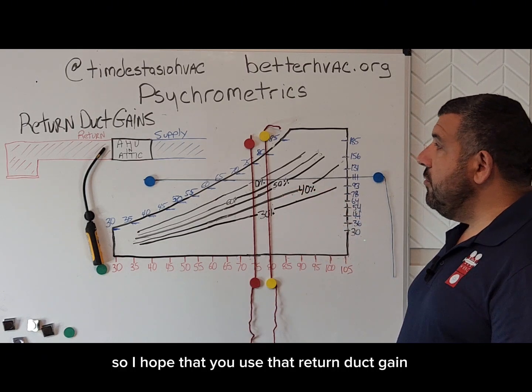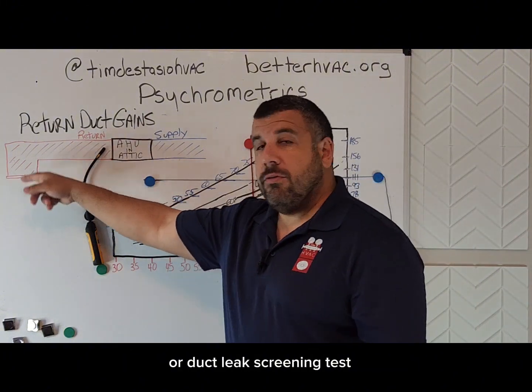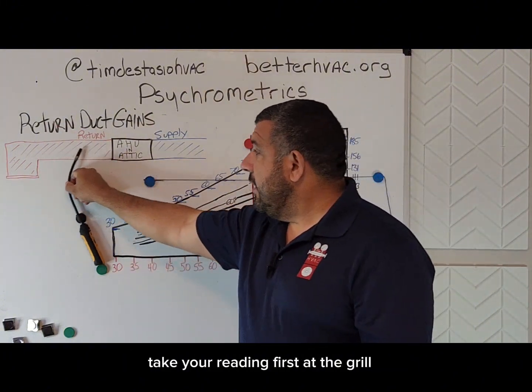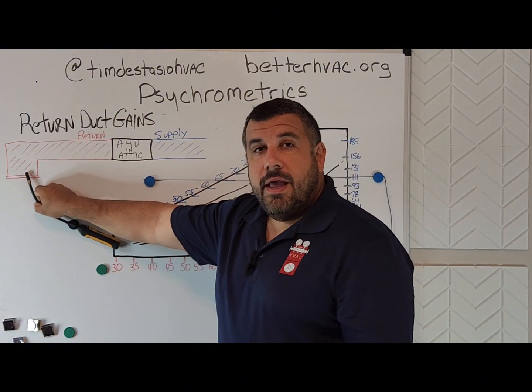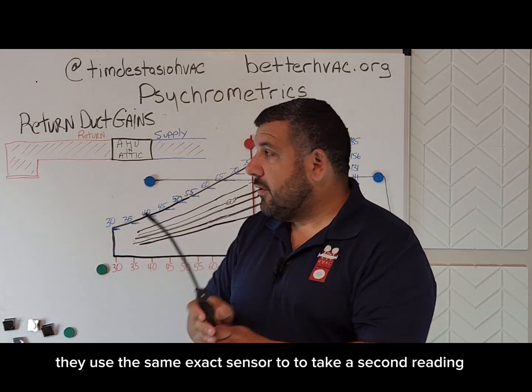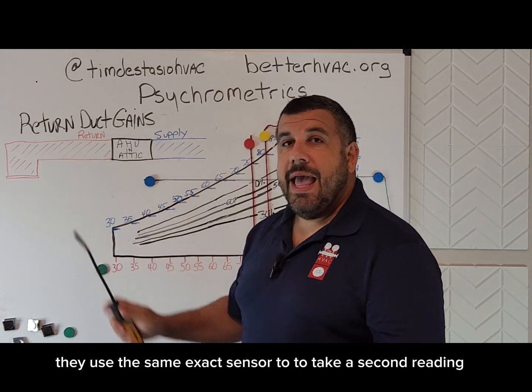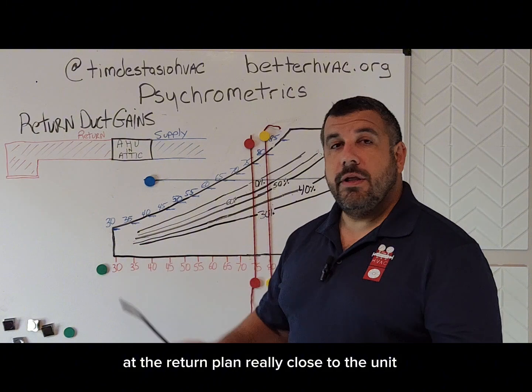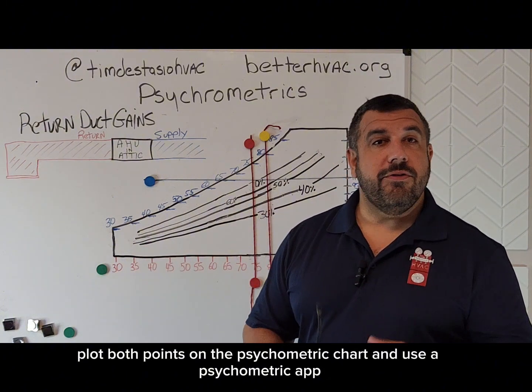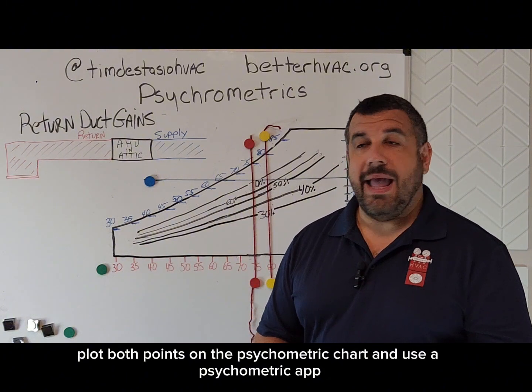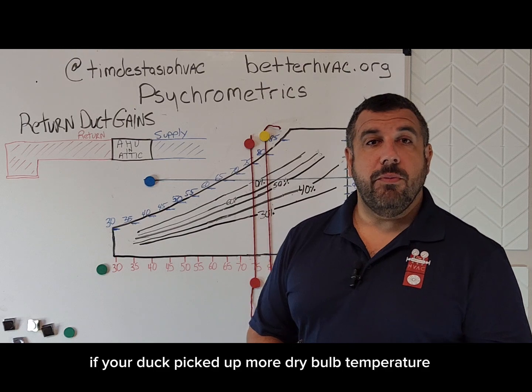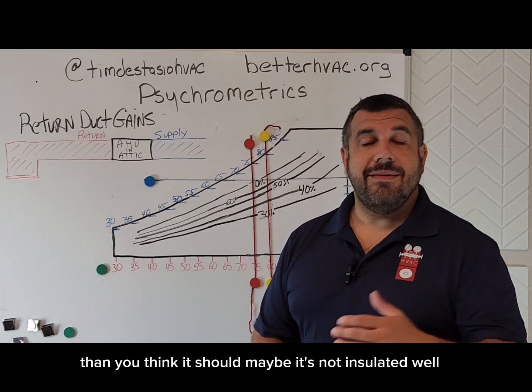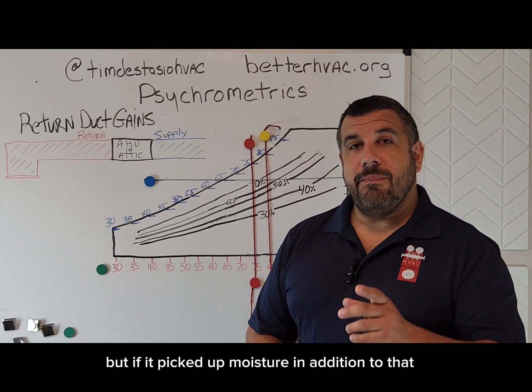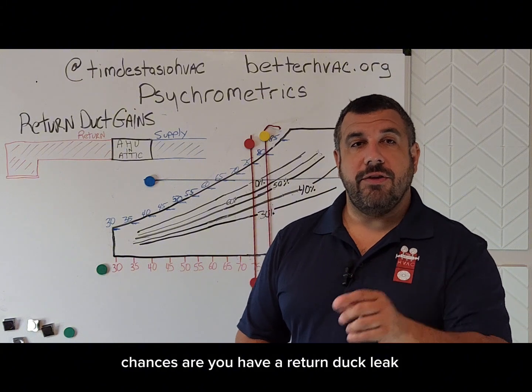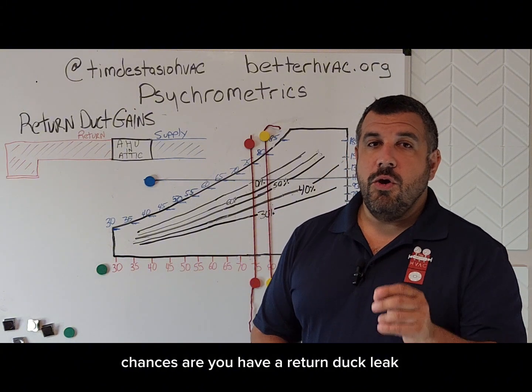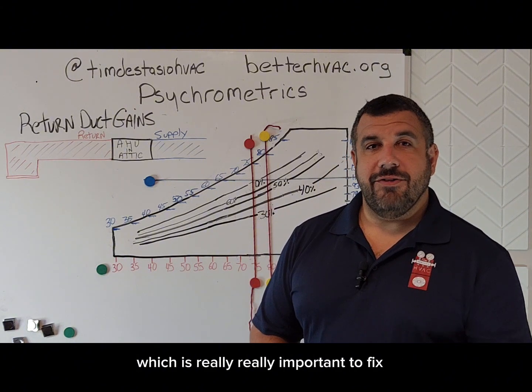So I hope that you use that return duct gain or duct leak screening test. Take your reading first at the grille, and then use the same exact sensor to take a second reading at the return plenum really close to the unit. Plot both points on the psychrometric chart or use the psychrometric app. If your duct picked up more dry bulb temperature than you think it should, maybe it's not insulated well, but if it picked up moisture in addition to that, chances are you have a return duct leak, which is really, really important to fix.